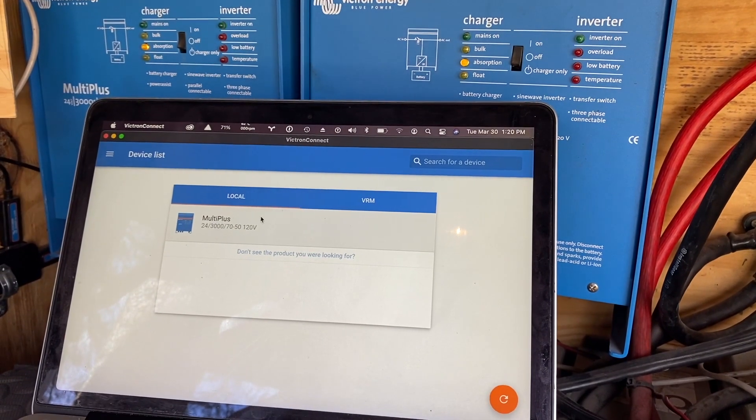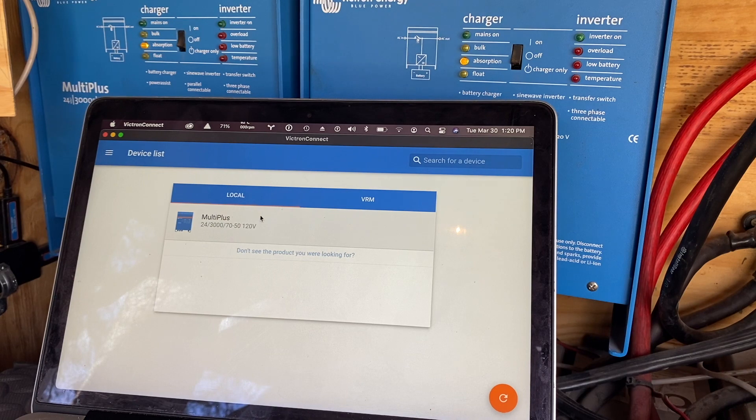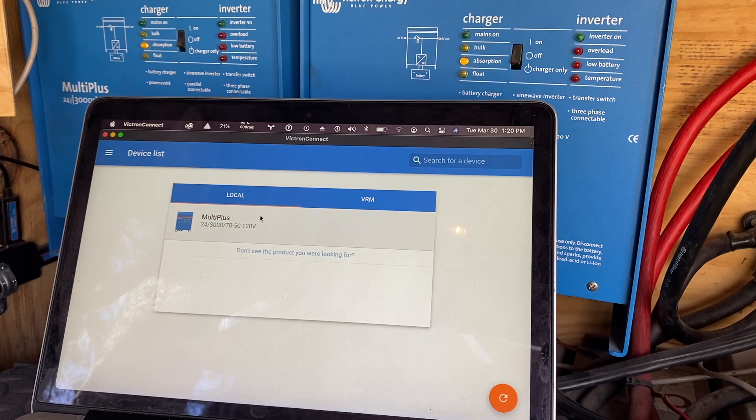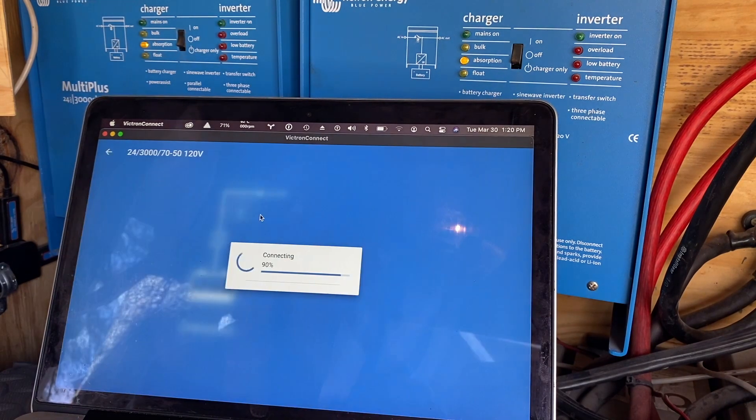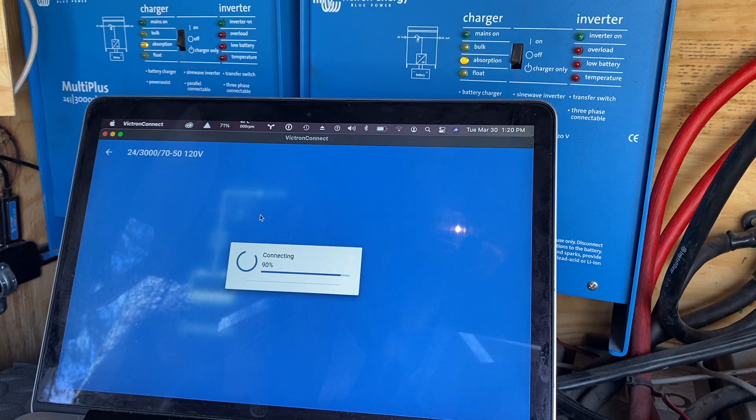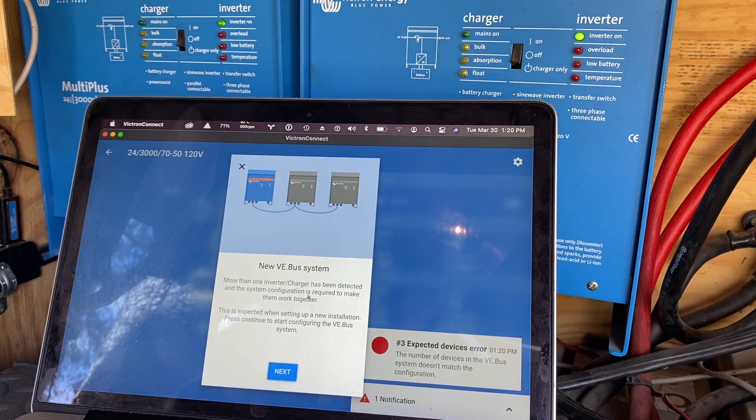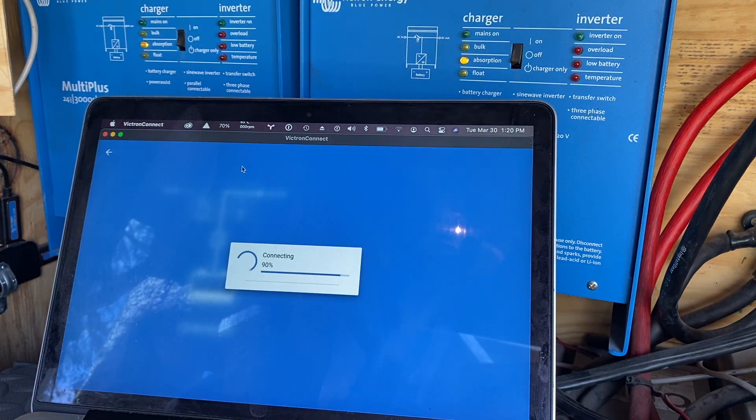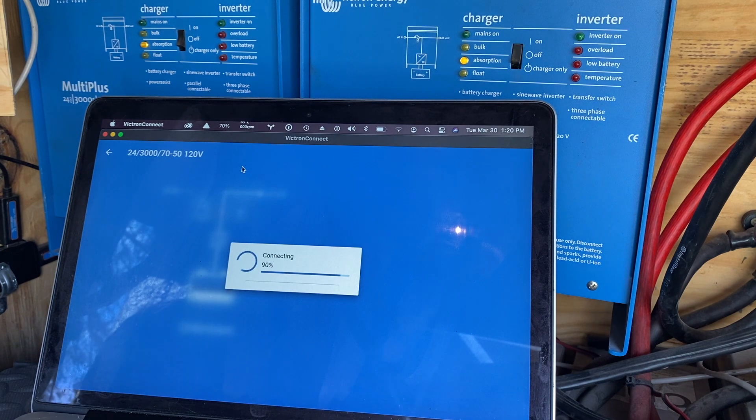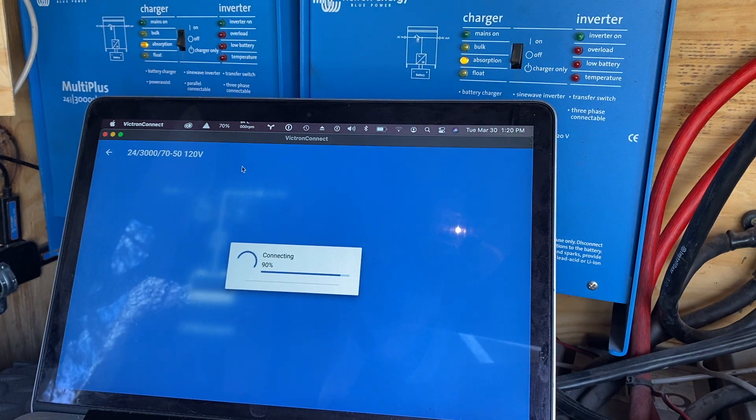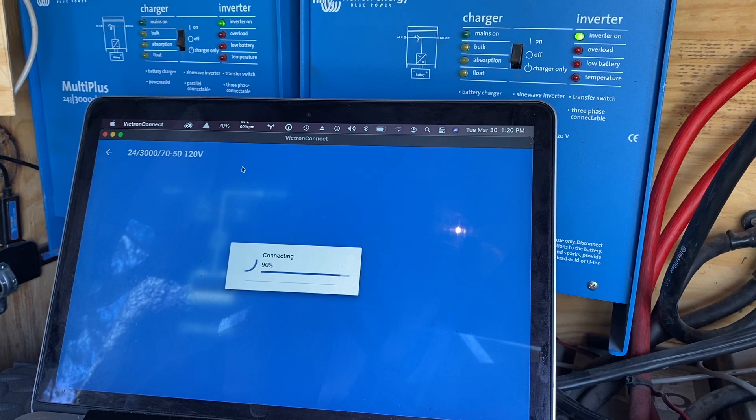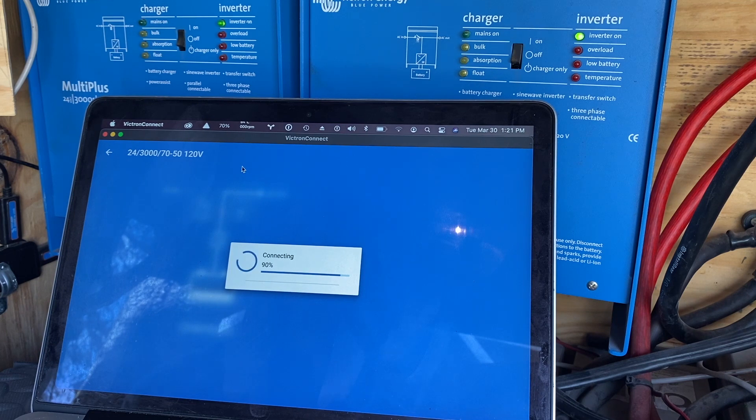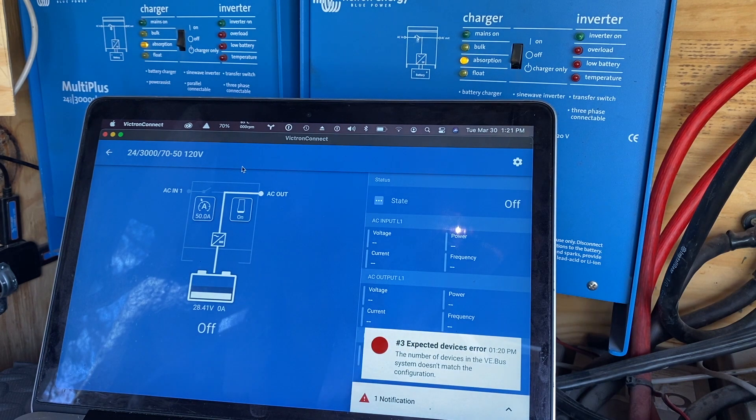I'm going to show the two lights there. It looks like they're blinking, which generally I want to say that blinking means that they are out of sync as far as firmware is concerned. It wants us to reset up the VE Bus, but I don't think we want to do that yet. I just want to verify that the firmware is loaded on both of them.